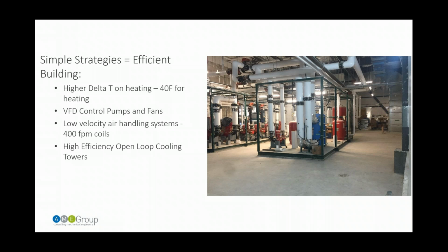High efficiency open loop cooling towers, water side economizer. And so just combining all of those strategies has really helped our efficiency numbers. The next one that we did that took a little while was recovering exhaust air heat. So the district energy lets us recover heat, but the issue is that they wouldn't let us recover heat through an active means with chilled water.